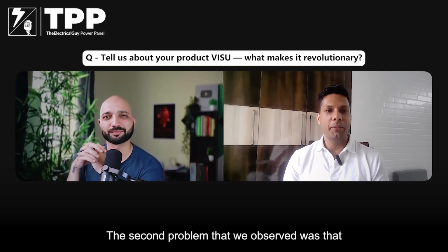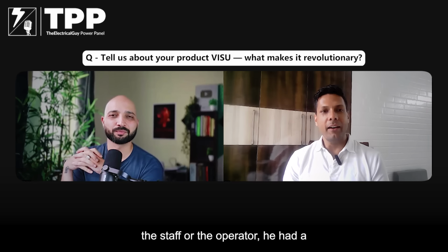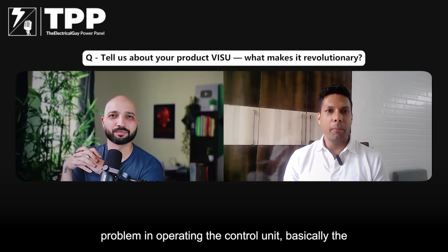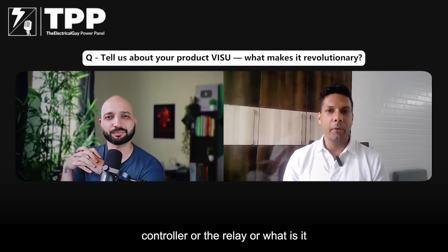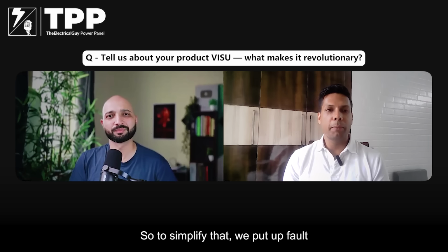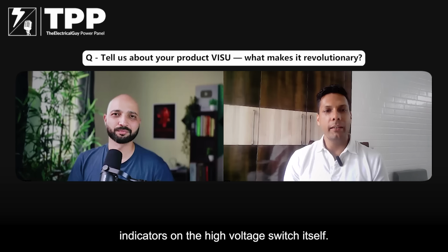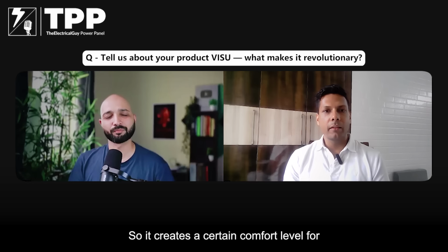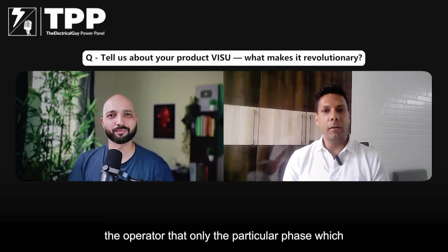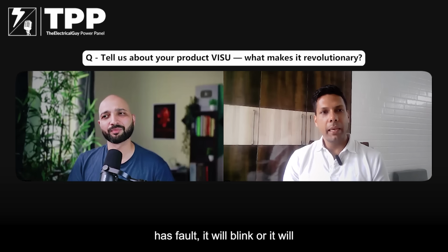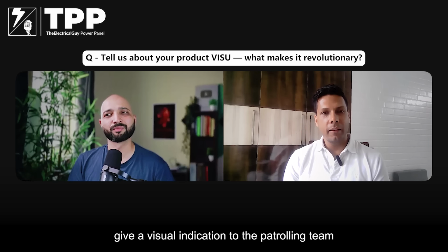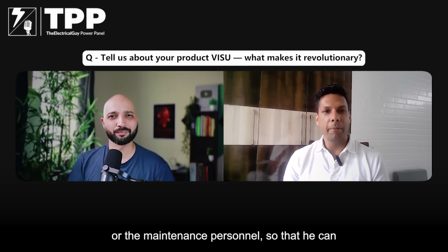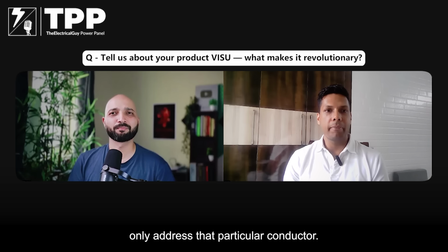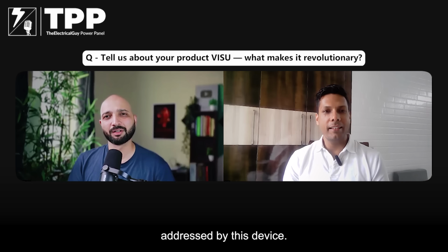The second problem that we observed was that the staff or the operator had a problem in operating the control unit, basically the controller or the relay, or whatever it is called. So to simplify that, we put fault indicators on the high voltage switch itself. So it creates a certain comfort level for the operator: only the particular phase which has the fault will blink or give a visual indication to the patrolling team or the maintenance personnel, so that he can address only that particular conductor. So these are the two challenges that are addressed by this device.